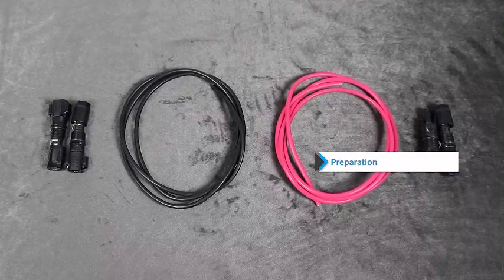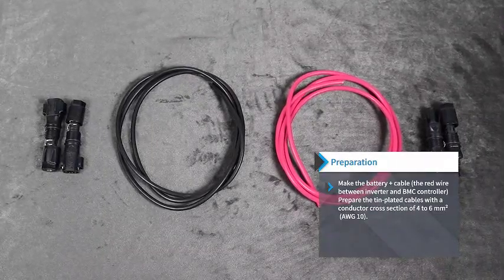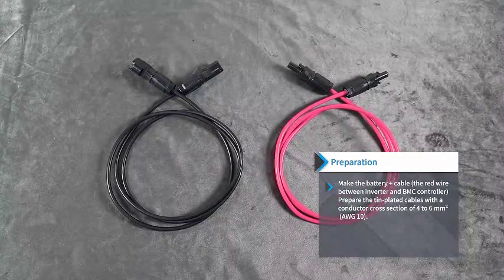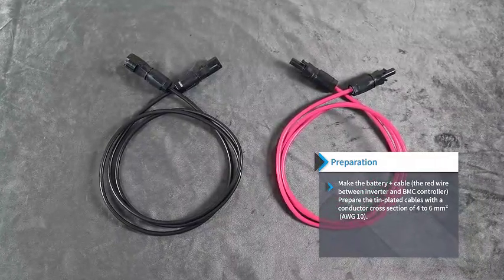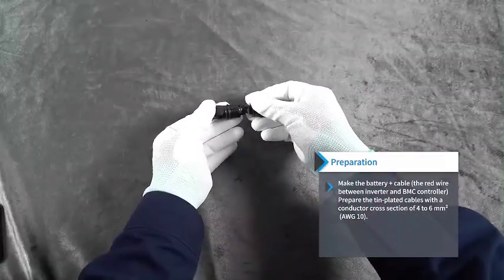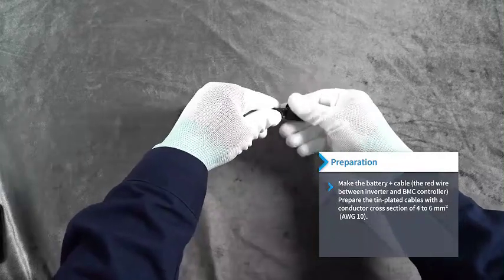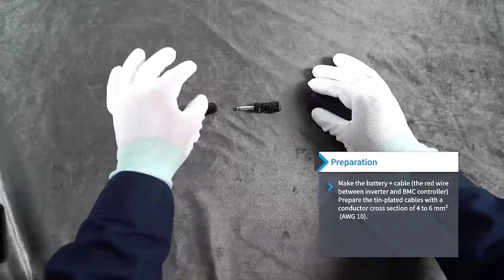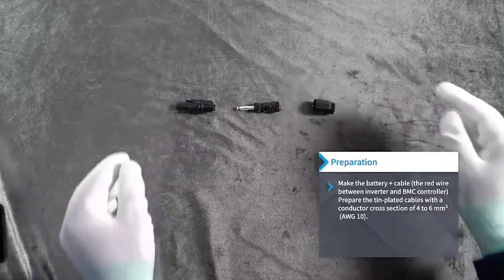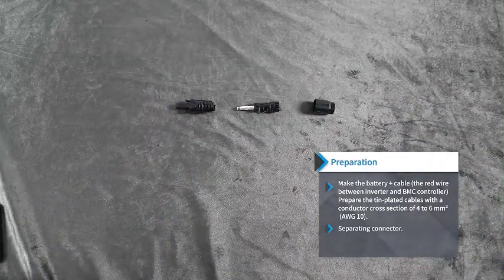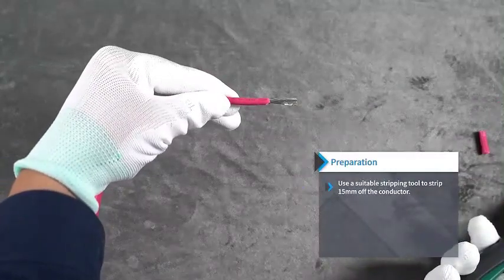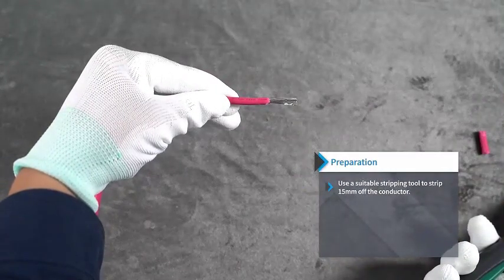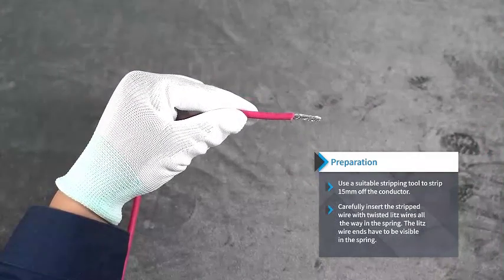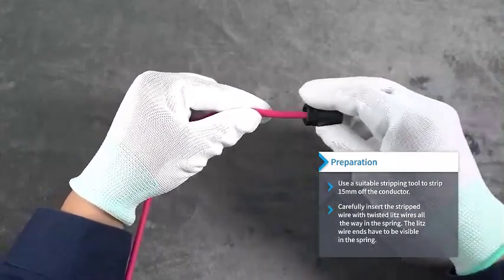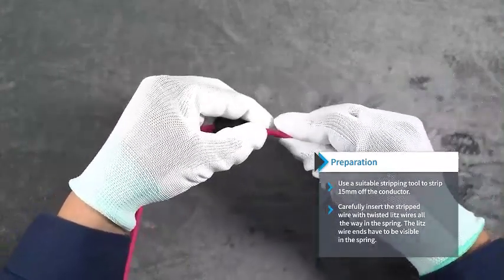Electrical connections. Preparation. Make the battery positive cable, the red wire between the inverter and the BMC controller. Prepare the tin-plated cables with a conductor cross-section of 4 to 6 millimeters squared, AWG 10. Use a suitable stripping tool to strip 15 millimeters off the conductor. Carefully insert the stripped wire with twisted Litz wires all the way into the spring. The Litz wire ends have to be visible in the spring.